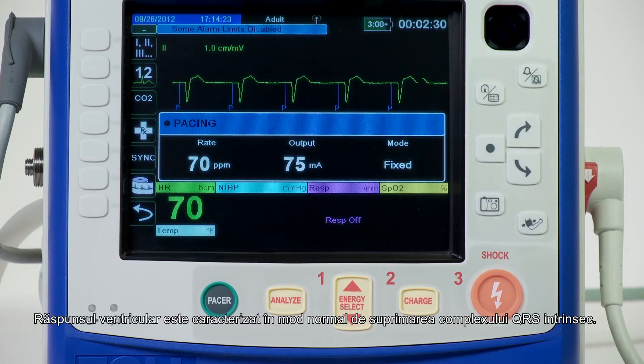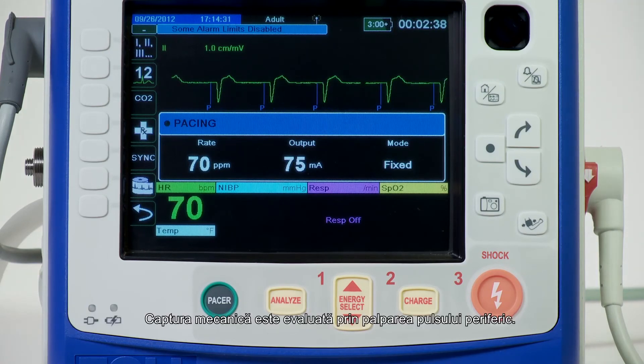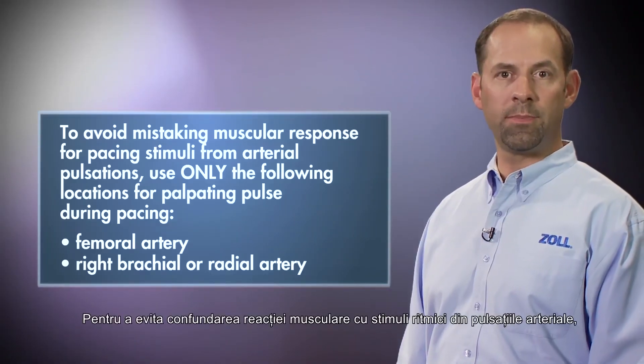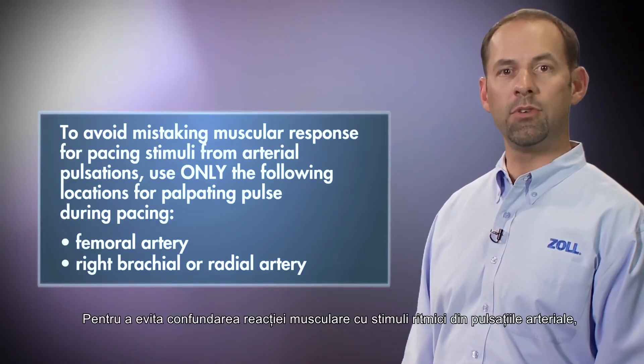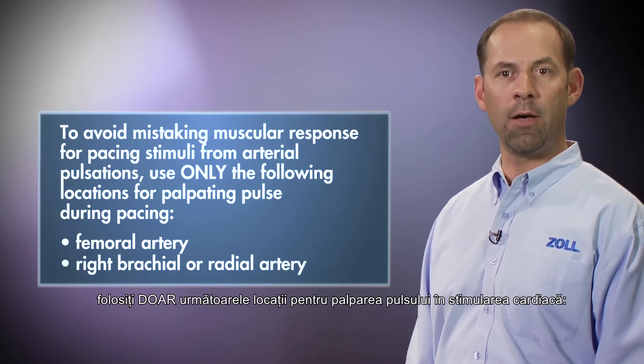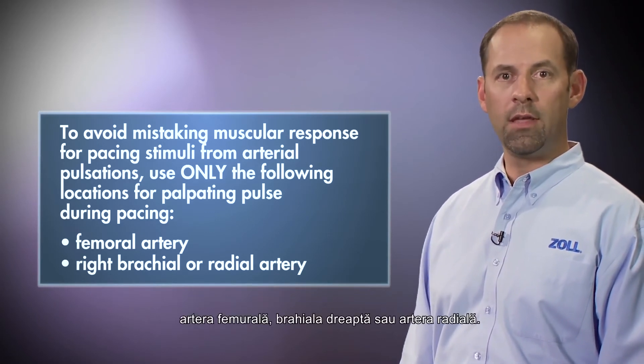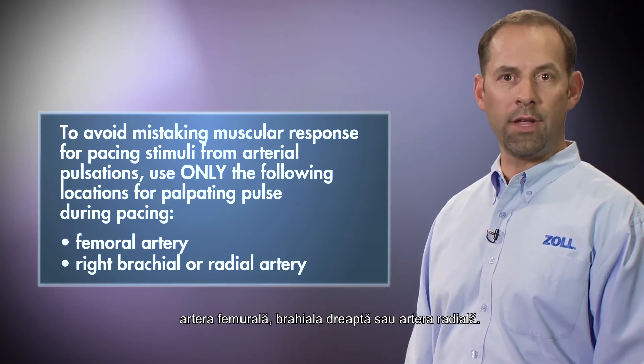Ventricular response is normally characterized by suppression of the intrinsic QRS complex. Mechanical capture is assessed by palpation of the peripheral pulse. To avoid mistaking muscular response for pacing stimuli from arterial pulsations, use only the following locations for palpating pulse during pacing: femoral artery, or right brachial or radial artery.